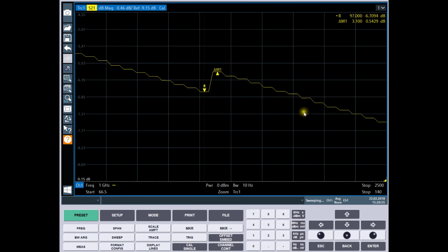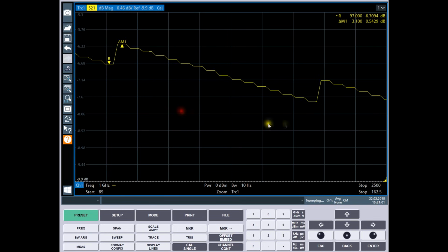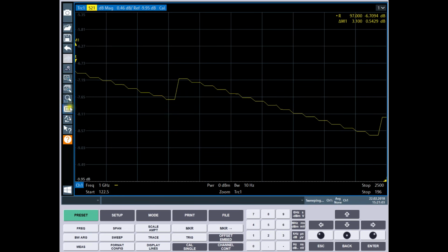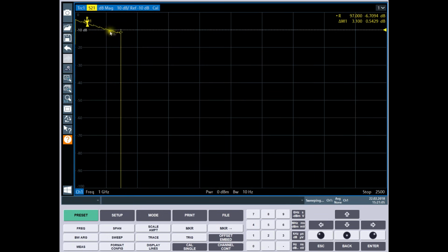So again, very close. Now, this is at a reasonably low loss. This is at -5 dB loss. So these steps are going to be very clear. If I go ahead and go back to zoom, you can see it's slowly working its way down. Now we are at a 10 Hz IF bandwidth, so the steps take about 200 milliseconds, and I have to give time for the attenuator to settle and make more than one measurement. So we are sweeping very slowly and moving along.